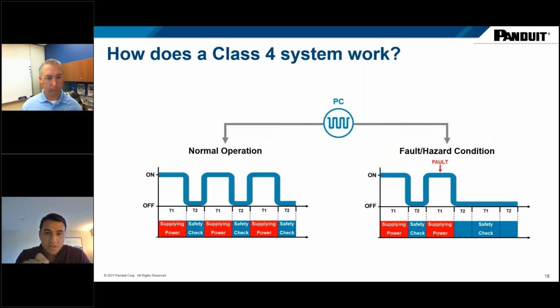So I want to take a closer look at that pulse current in the center, what's really flowing through that cable. And here I'm just showing you one way a system could work. On the left, we're zooming into that pulse, and this is normal operation. If you think of the y-axis as an on-off, power on and off, and you're doing that so quickly in specified time periods, this power reaches the converter, gets rectified, and powers the end devices. The end devices don't see this pulsing at all.